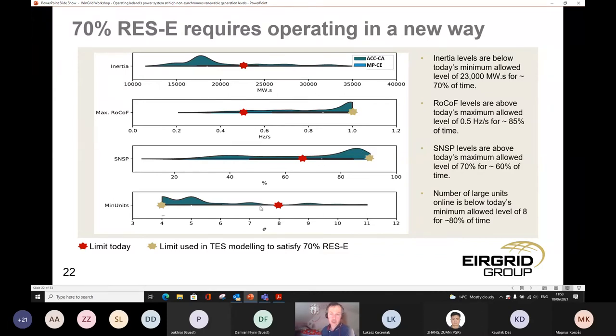And then a fourth limit that we have, I didn't mention earlier, but we have a rule at the minute that we have to have 8 large conventional generators on the system - so either large combined cycle gas turbines, or oil or coal units, on the system for system stability purposes. But we need to be able to reduce that, to essentially make more room for wind to be able to connect onto the system.